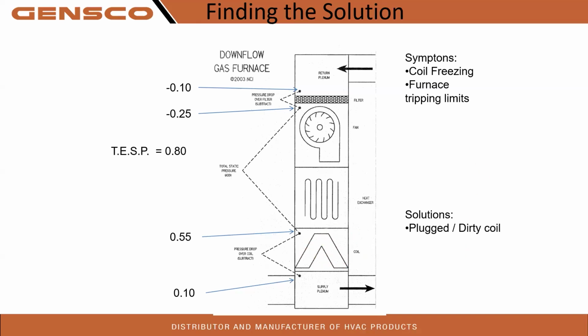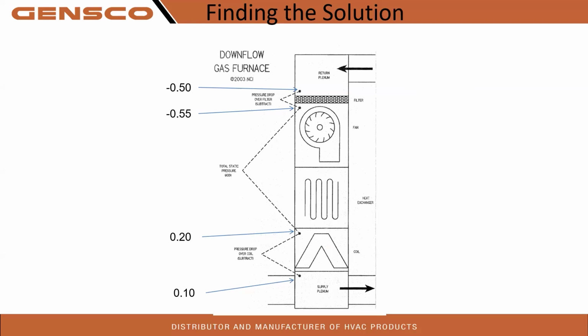They ran it during new construction. Undersized coil. We have seen that, where I've seen some 2-ton coils installed on 3-ton systems. So we got an undersized coil, we just can't handle the airflow over it. Let's see what this one is. Another downflow gas furnace. We got 0.5 on the return. 0.55, so the filter is okay.